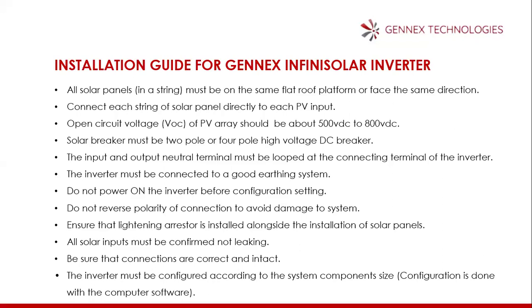directly to each PV input. Like I mentioned before now, the inverter has 4 inputs, 2 inputs per charge controller. So each string is connected directly from the roof to the input provided. Which means you cannot create a bus bar, join panels and loop all the inputs together on the bus bar. No, each input is provided to be connected to a string of panels.